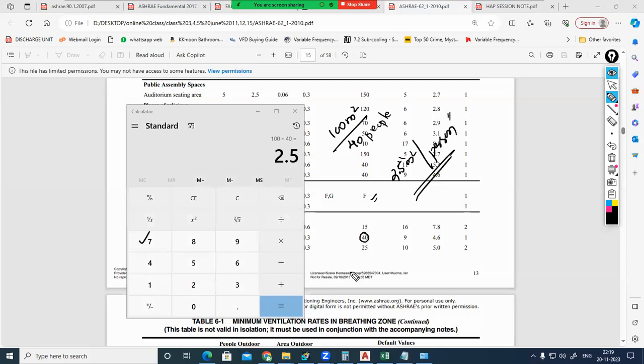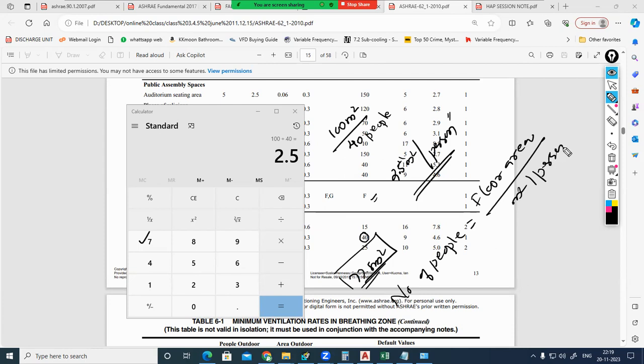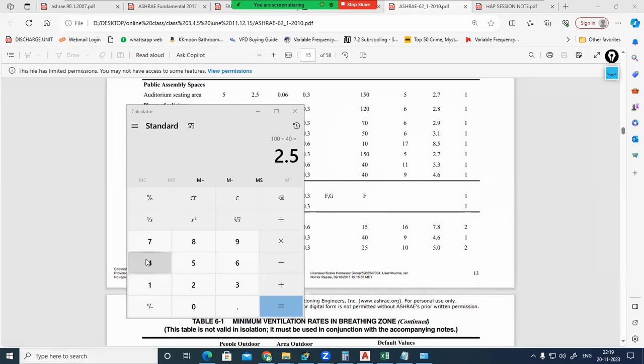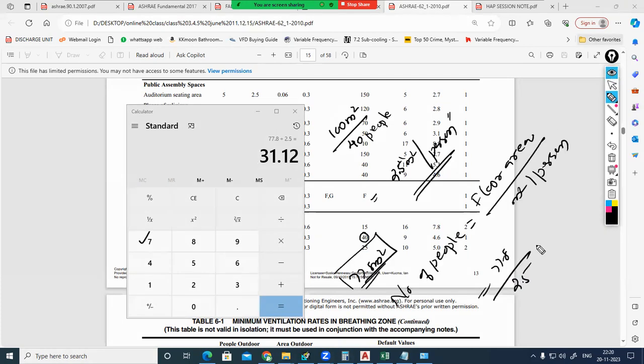For example, if this sales area has 77.8 meter square of floor area, then the number of people is equal to the floor area that we are designing divided by meter square per person. Floor area is 77.8 divided by 2.5 meter square per person. So the number of people will be 77.8 divided by 2.5, that is 31.12. 31.12 is not possible, so you can round that up to 32 people.